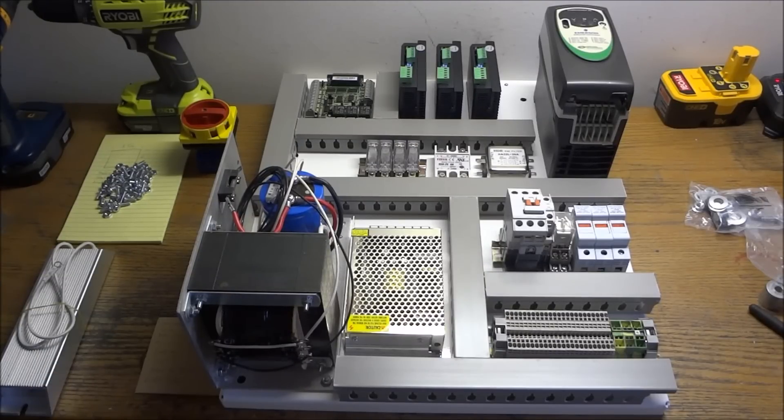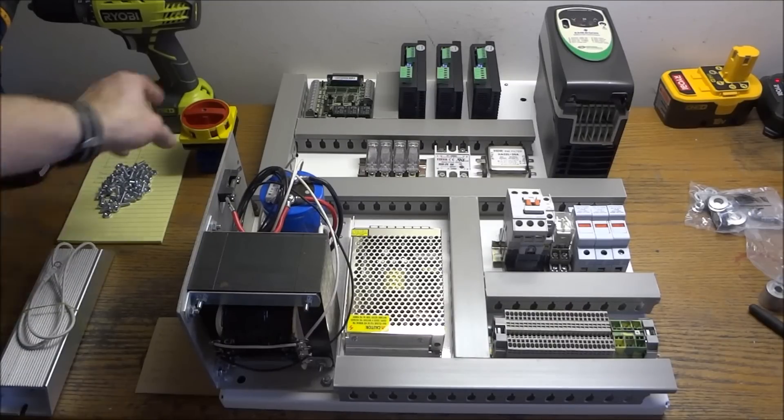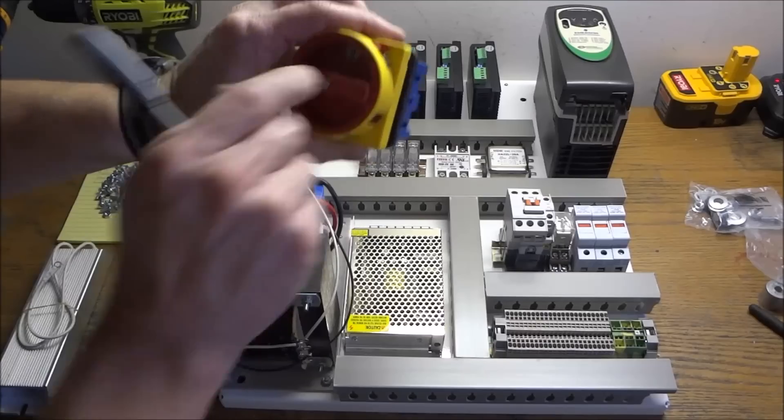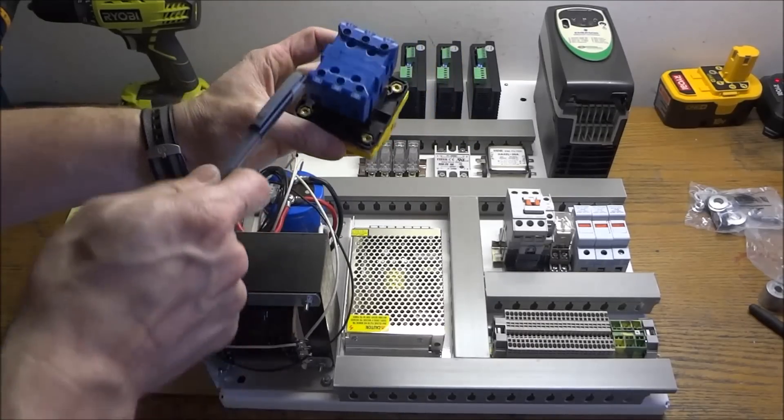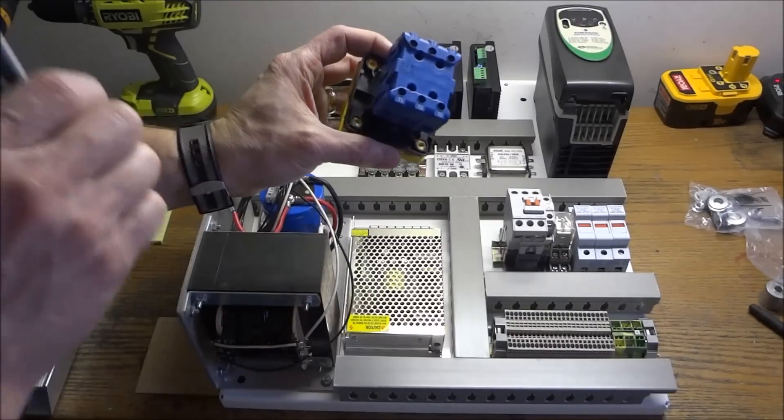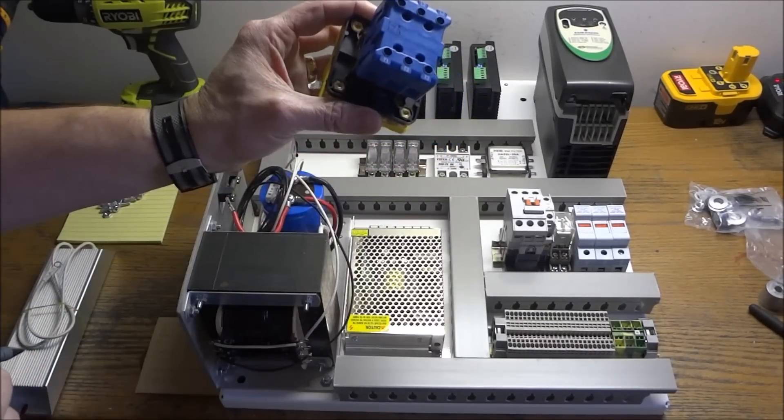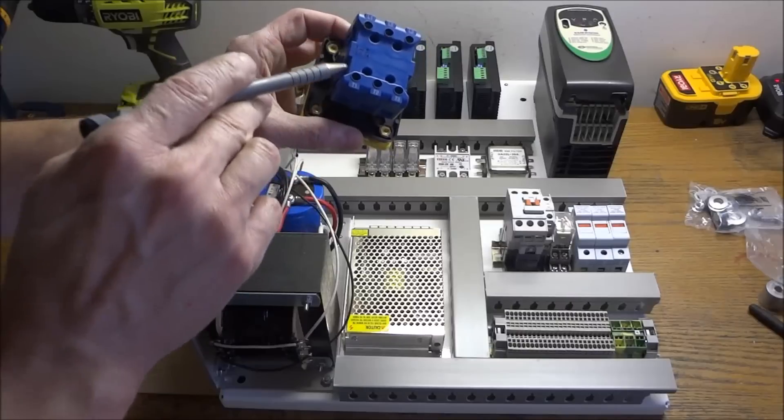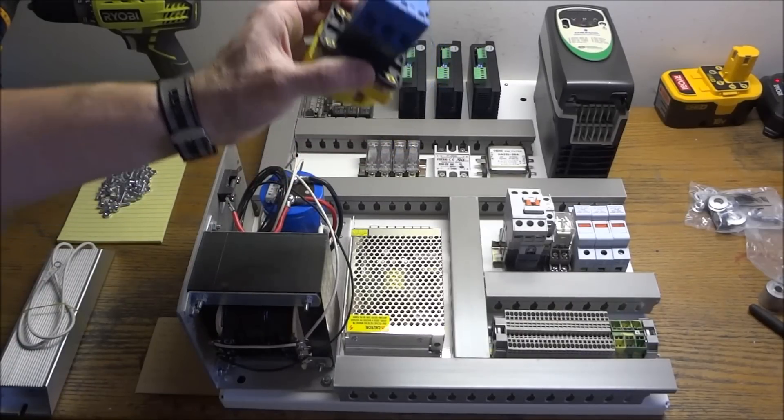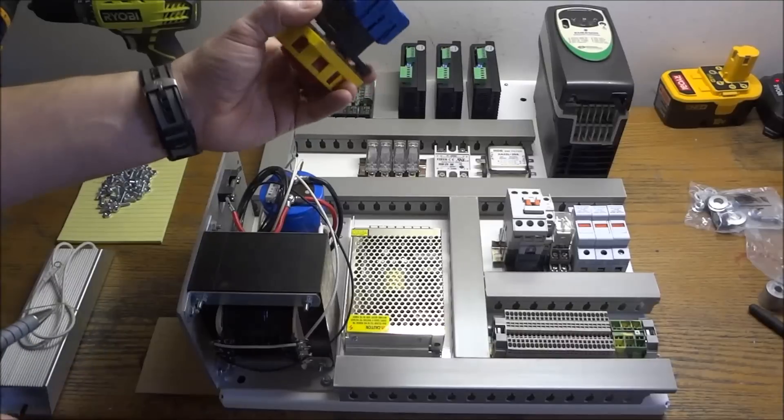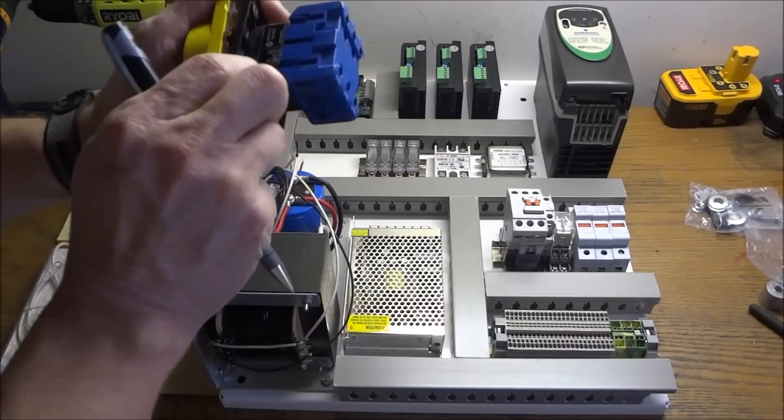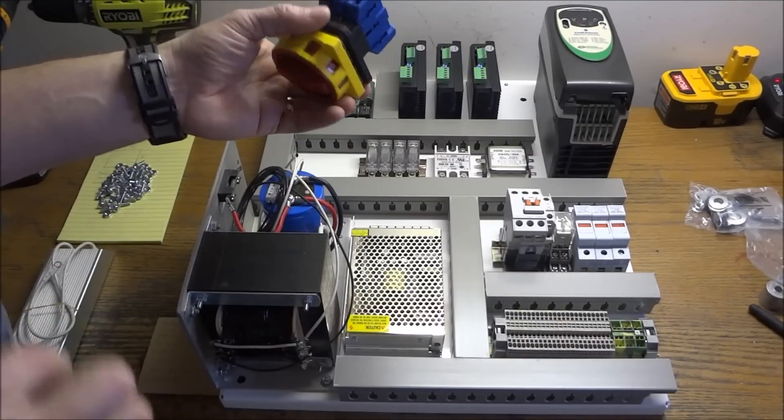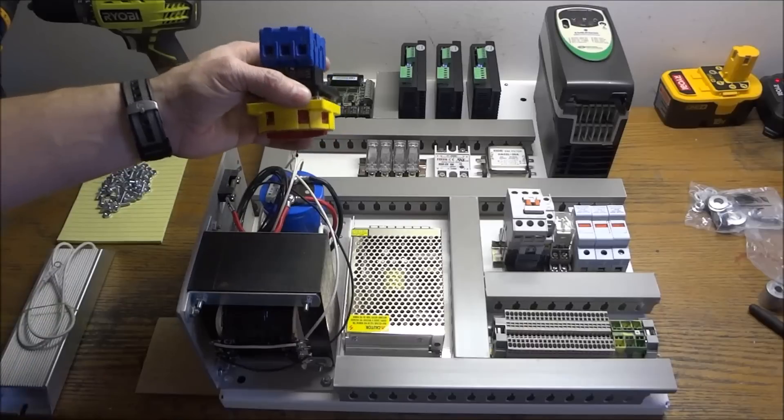The first item is our main disconnect, and this is just a rotary type disconnect. It basically has three different sets of contacts in here. This would be for like a three-phase panel, but we're only going to be using one set of contacts. I could have gone with something simpler, but this is what's used in the industry, and if I decide later on to go with maybe a 220 VFD, I'll have the other set of contacts here.